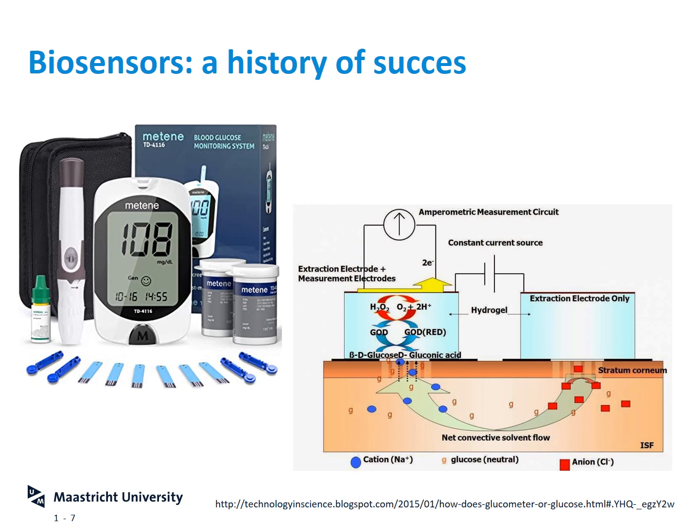Now, to give you a brief overview of what you can use biosensors for in everyday life, I will start by giving you some very famous examples that are used everywhere in modern day society and that you might not even know were biosensors to start with. Now, the most striking success story is the blood glucose meter for diabetics. This blood glucose meter consists of a dipstick where you can add a drop of blood, and that dipstick contains two electrodes. On one of those electrodes, there is an enzyme called glucose dehydrogenase, and that glucose dehydrogenase will catalyze the conversion of glucose into gluconic acid.